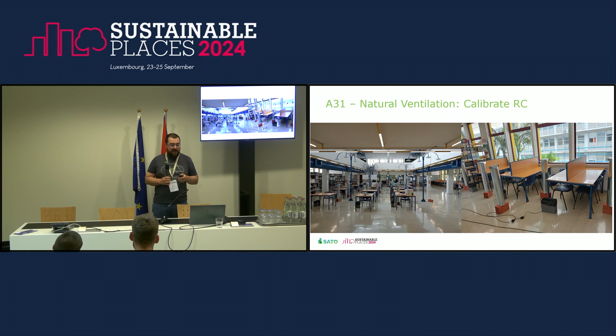Then to calculate airflow, we filled up the room with CO2 — a predetermined amount, enough to be measurable but not too much to be dangerous, otherwise no one would do the math afterwards. So we have these fans to distribute the CO2 in the building. We have this one, and that other small one, which is the same size, just farther away.